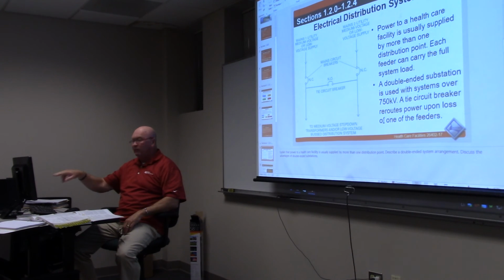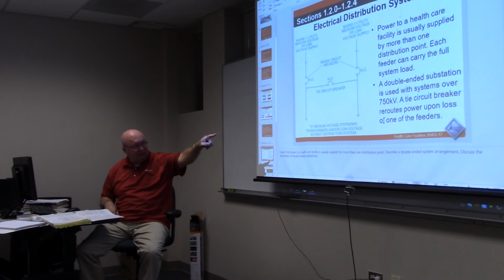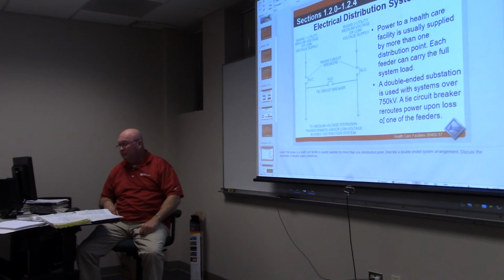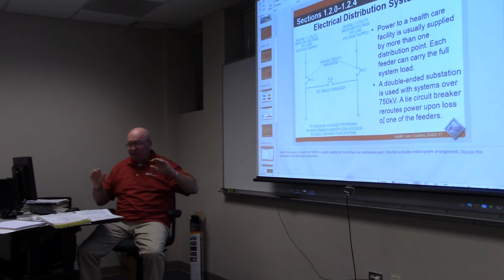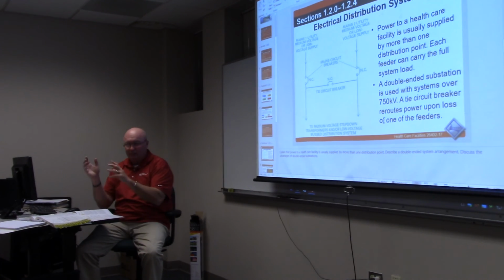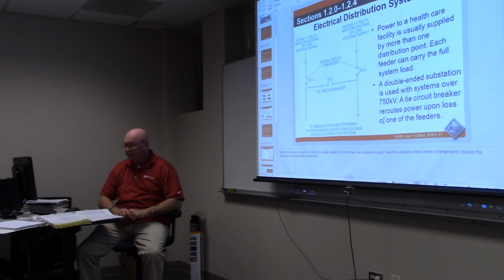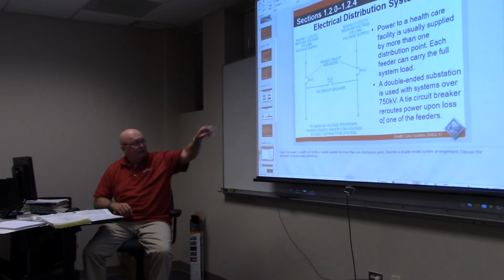It's redundant, a backup to a backup because of the load. A double-ended substation is used when a system is over 750 kVA. A tie circuit breaker reroutes power upon loss of one of the feeders, so if something happens to one feeder, the other automatically kicks over and uses the other feeder. That's what we got there with the double-ended system.